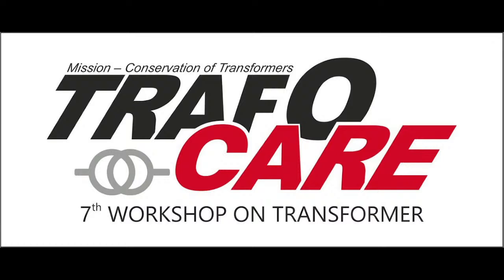Please add. See, for the fault current, you need to understand what the system impedance is. You need to understand what the transformer impedance is, because the fault is not going to occur only at the principal tap, and the impedance also varies between the various taps.